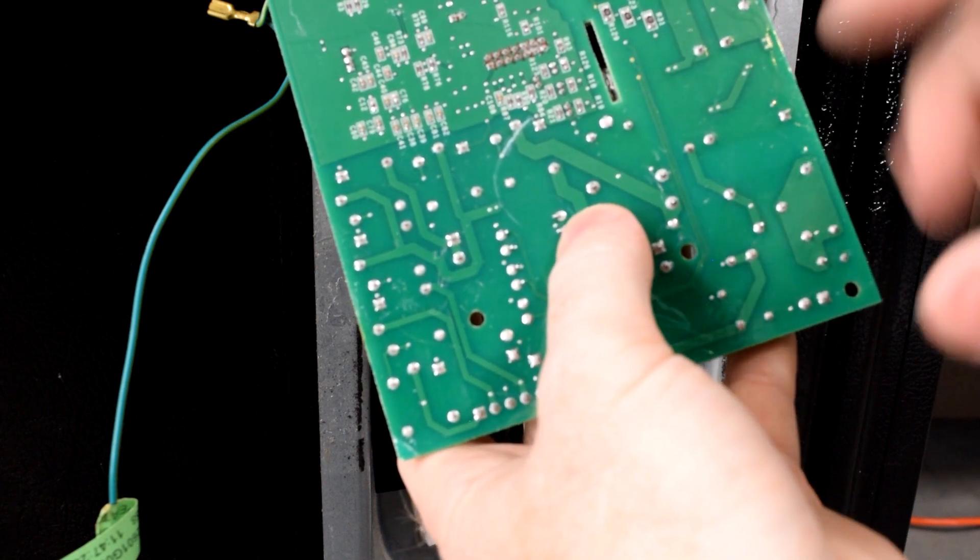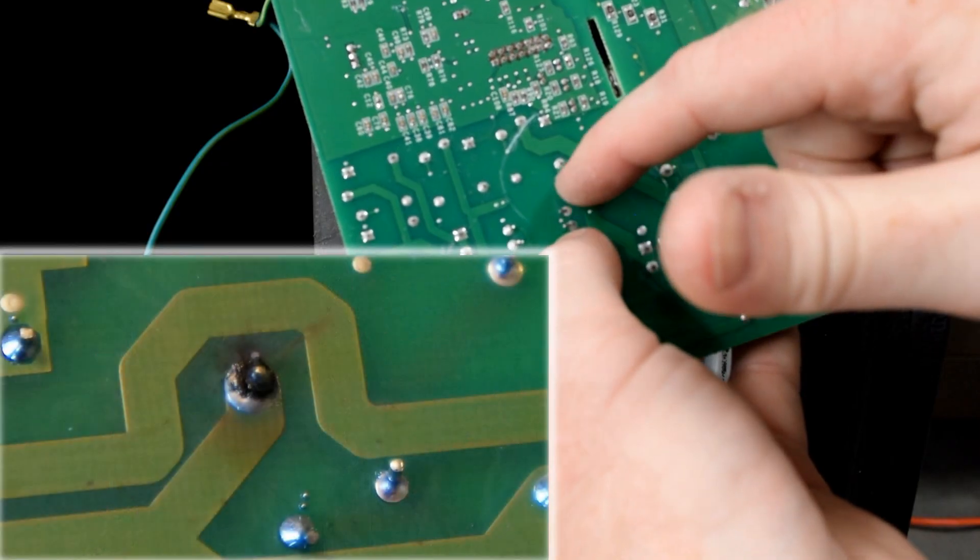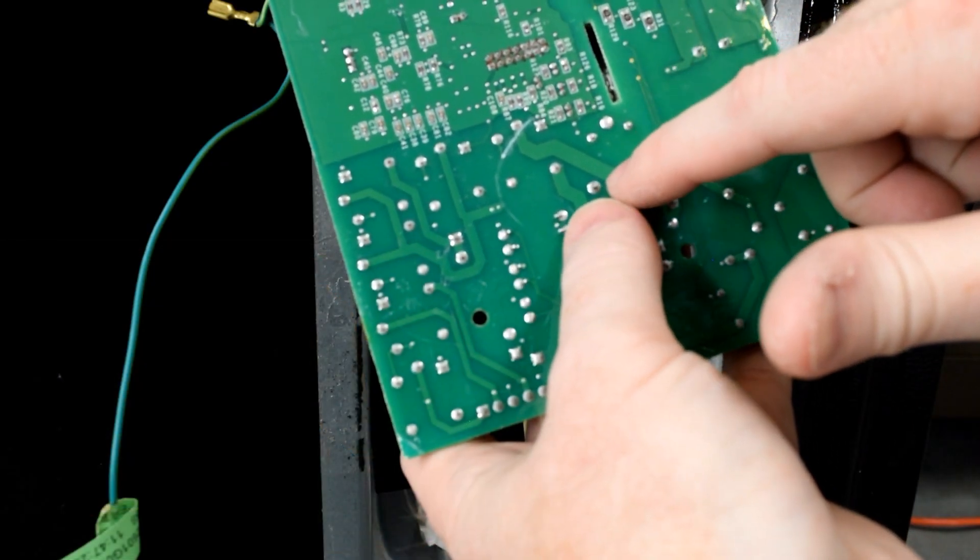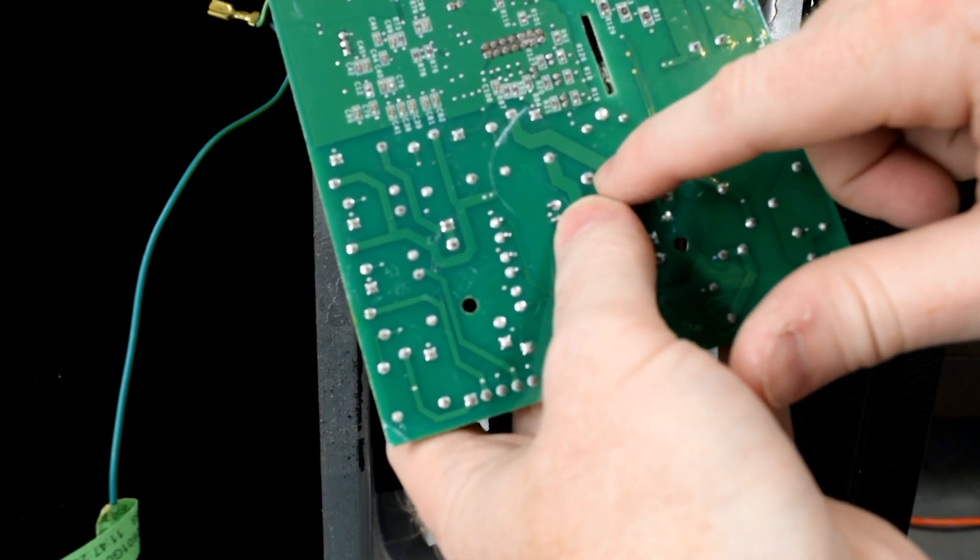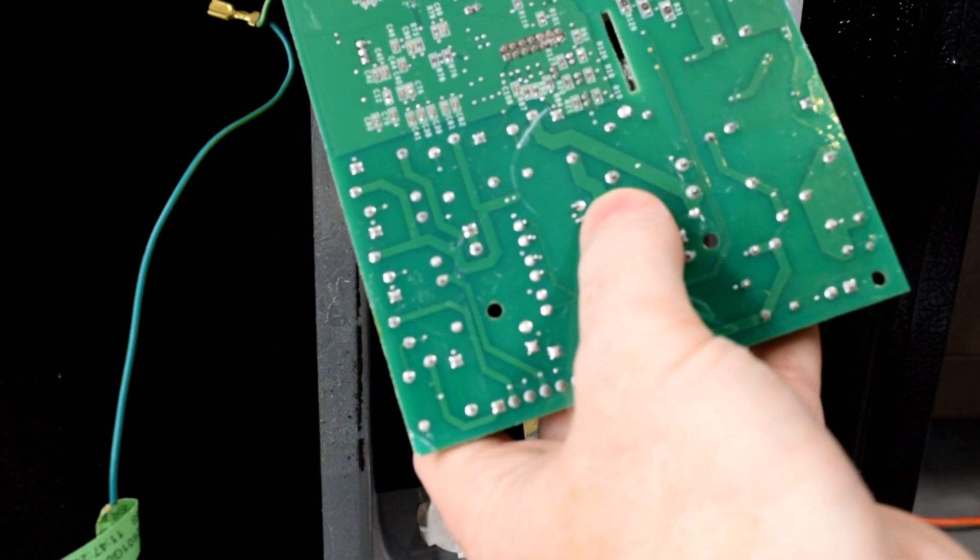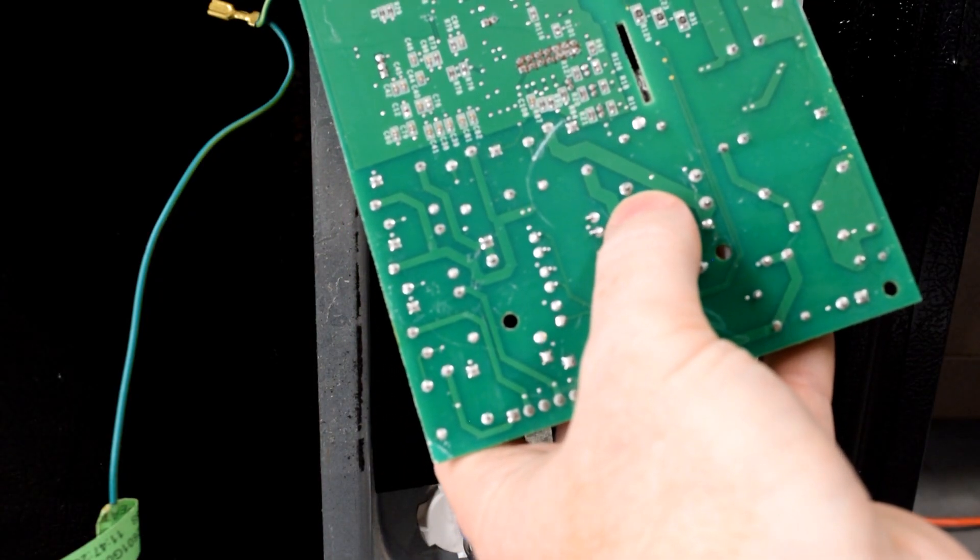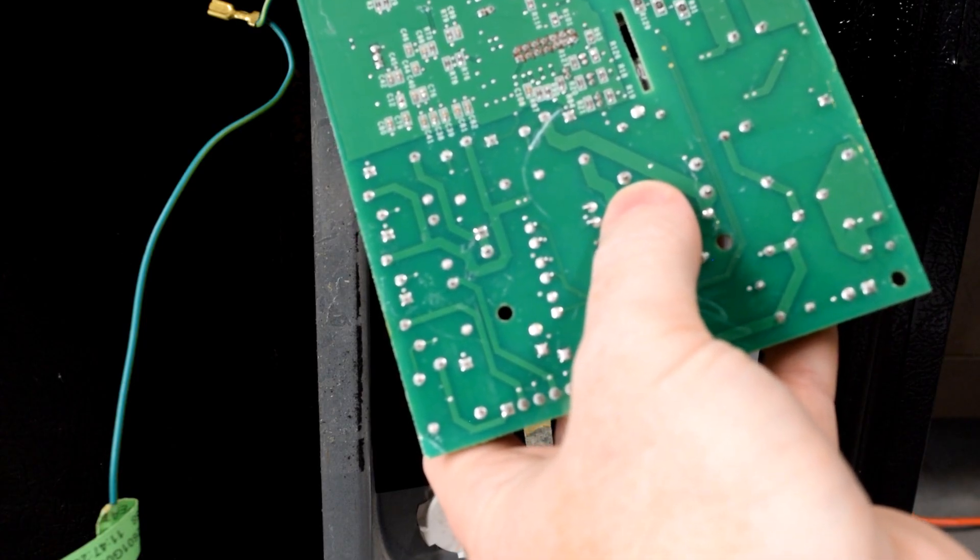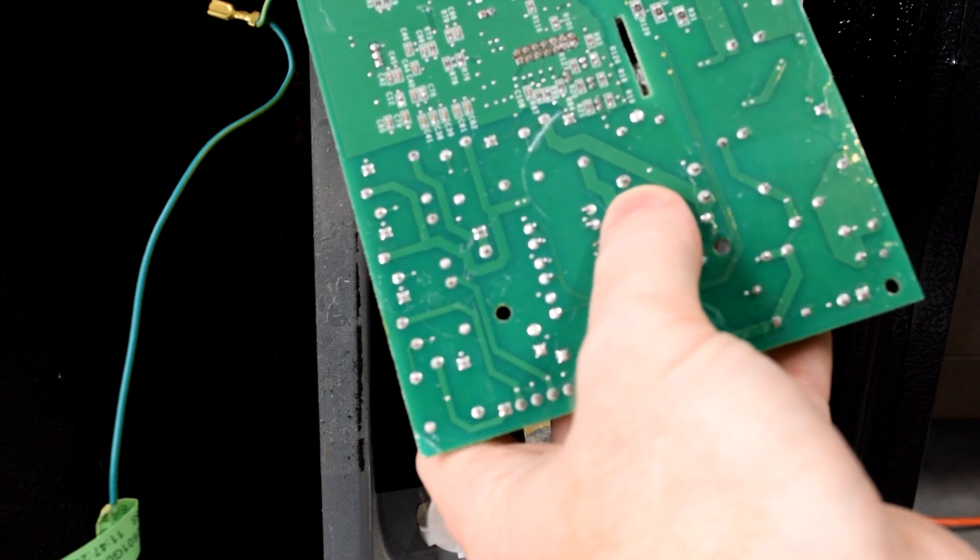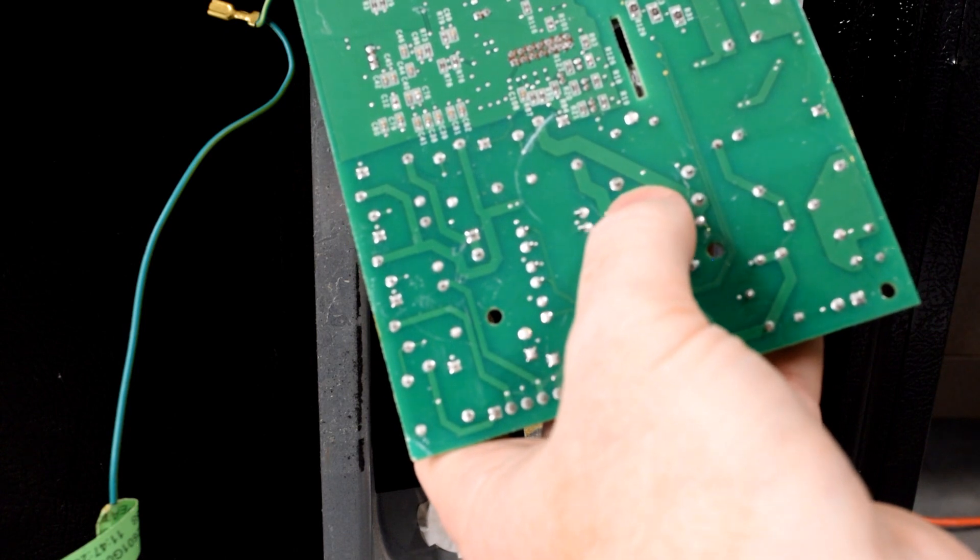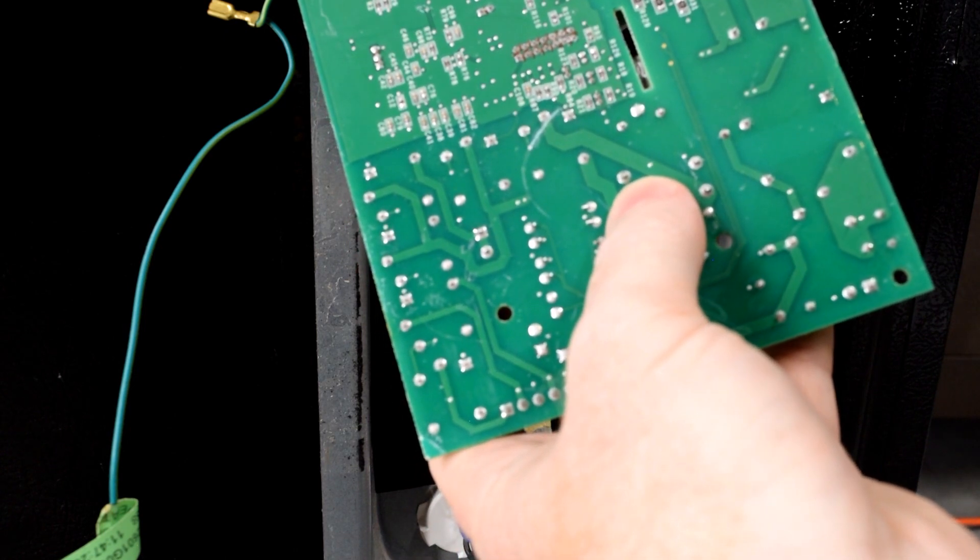And you'll be able to tell, it'll be quite a bit of carbon buildup, looks like a small bonfire happened right there, or sometimes it's just the solder has melted. Now if that's the case, some people are tempted just to add solder to that and get it working again, and it may work temporarily, but that burned solder joint is an indicator that the relay itself is getting weak. It's running at too high of resistance, causing too much heat, and thus you get the melted solder joint. So if you find that it's burned in that spot, either you need to rebuild the control board or buy a new one.